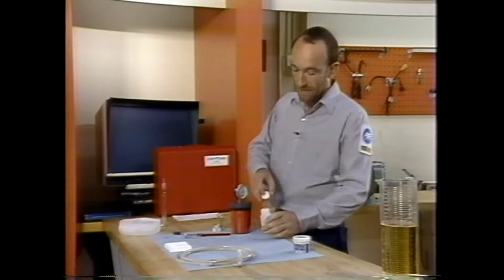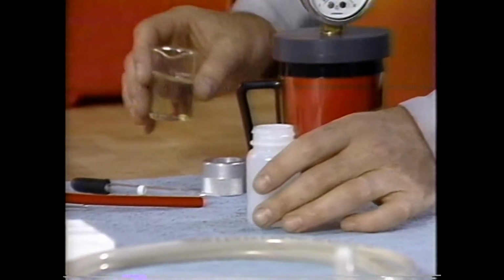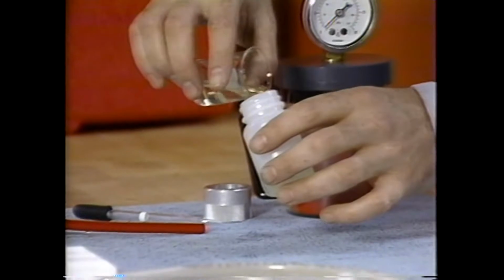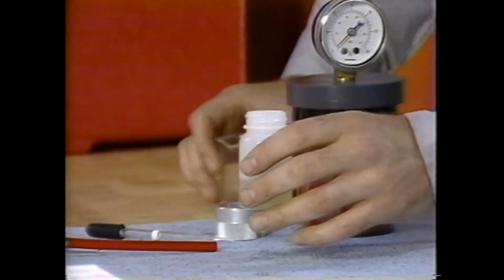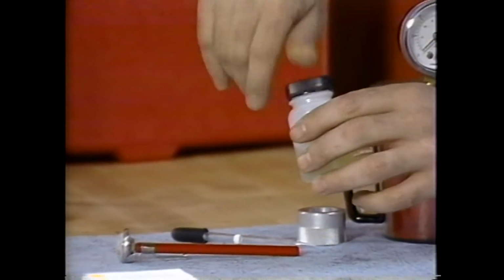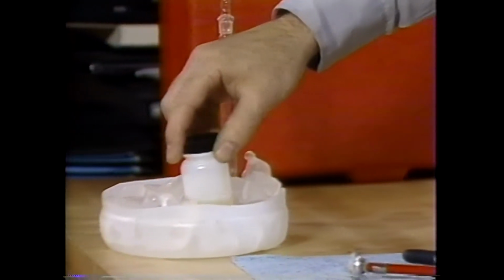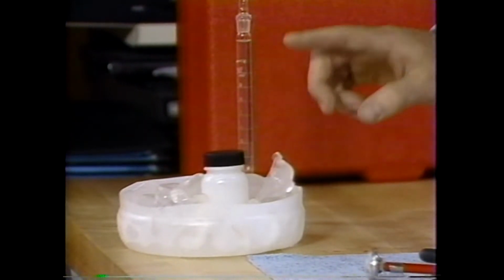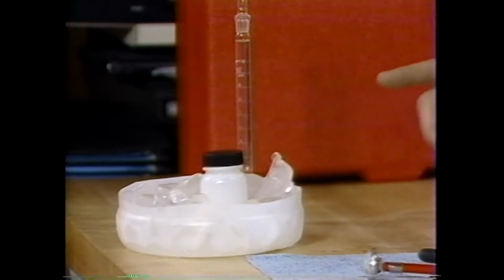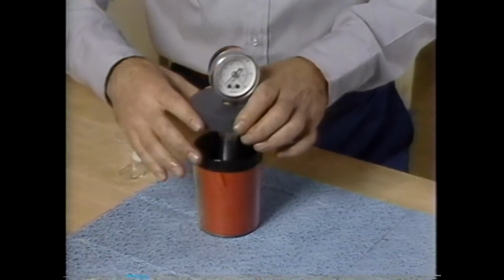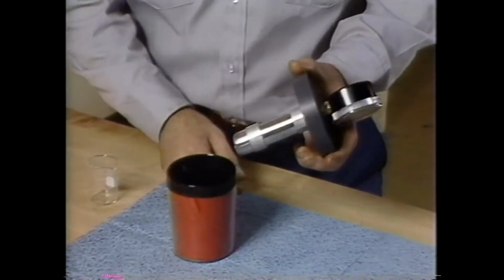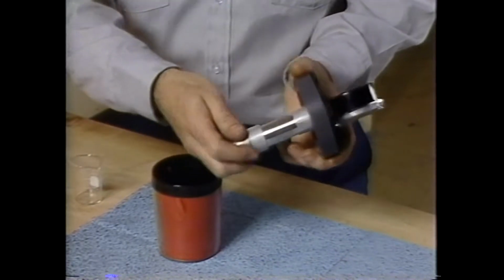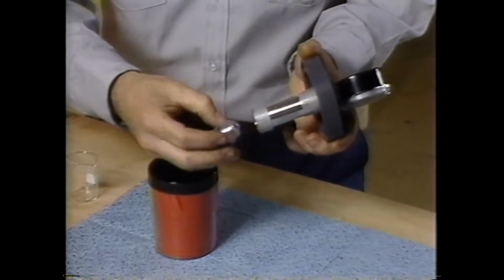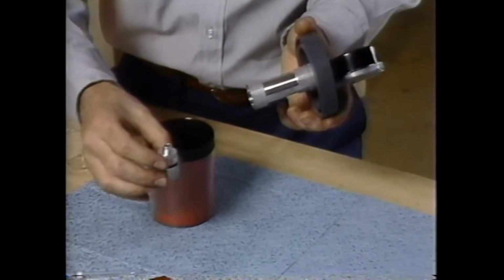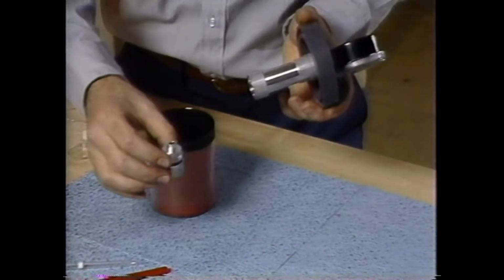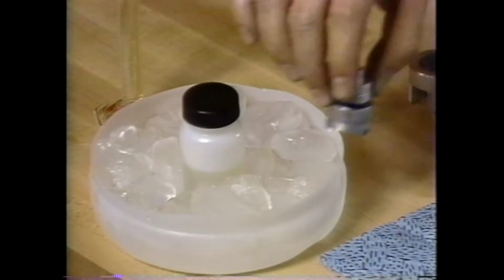First take the top off and pour the fuel to be tested in the container. And put the top back on and store the container either in ice or chilled water, something that'll cool the fuel down. And we're going to use this pressure tester here to measure the Reid vapor pressure of the fuel. In the bottom of this tester is the fuel cup. This is where we put the fuel to be tested. We want to chill this along with the gasoline, so we'll put it in the ice as well.